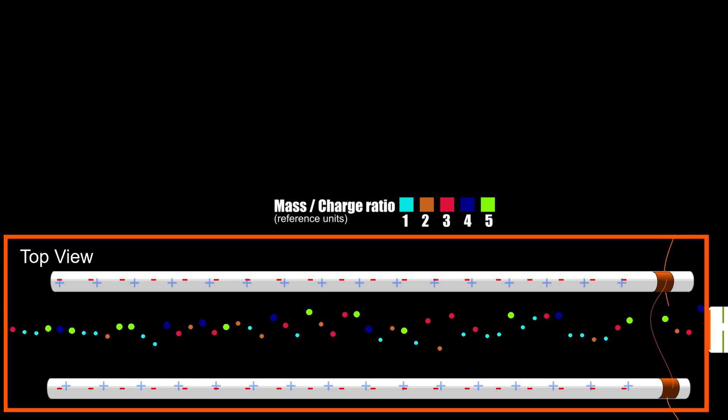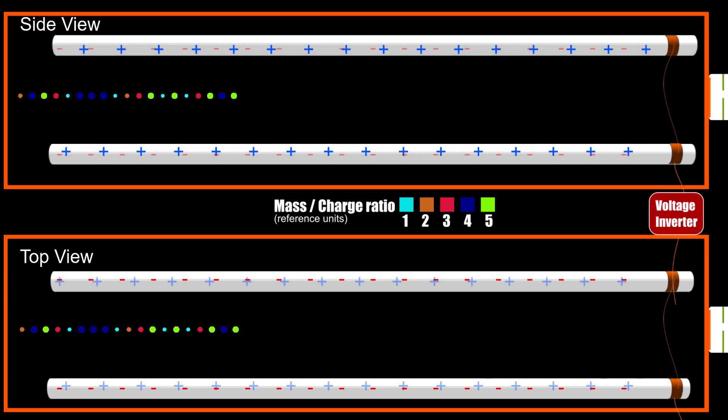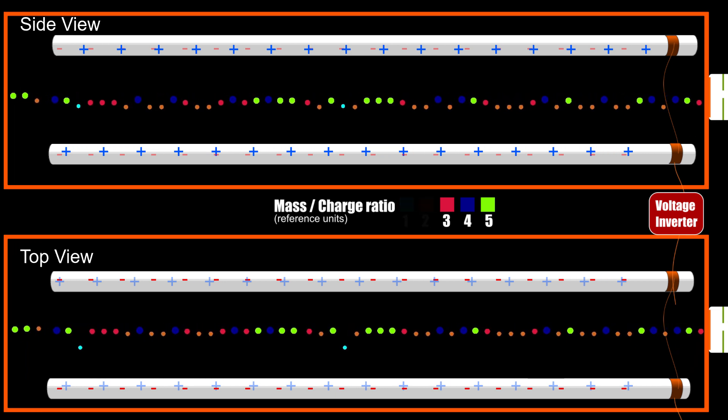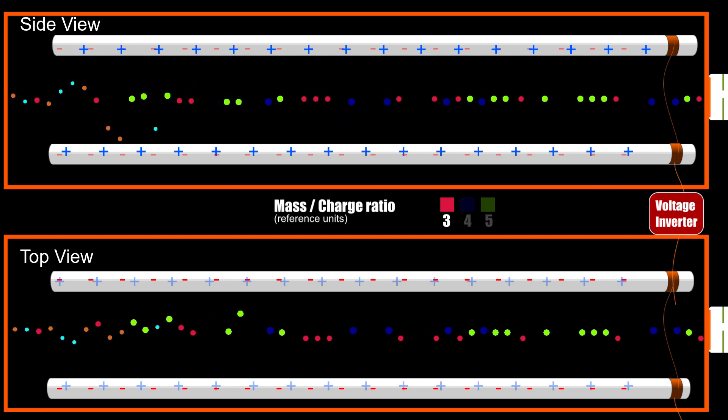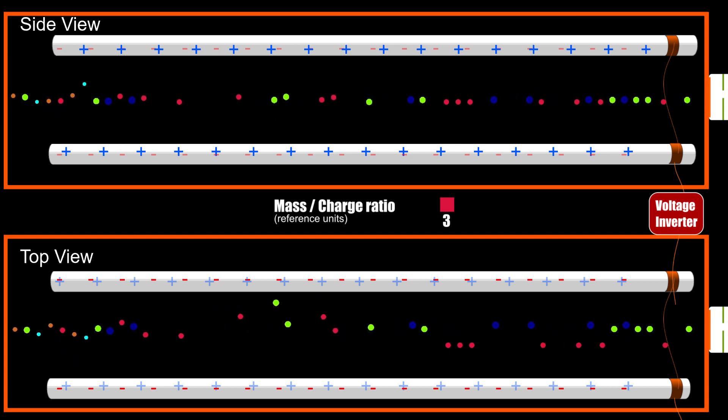So now, the second set of rods acts like a low-pass mass-to-charge ratio filter. If we now turn back on the first set of rods which operates as a high-pass mass-to-charge ratio filter, its effect will be combined with the effect of the second set of rods which operates as a low-pass mass-to-charge ratio filter. This combination effectively creates a high quality band-pass filter which can be tuned to a single mass-to-charge ratio value, effectively detecting a specific molecule.